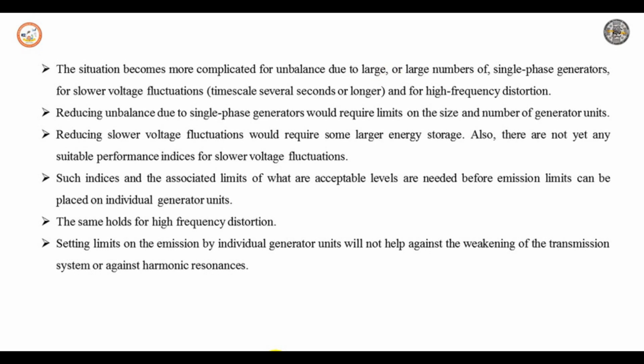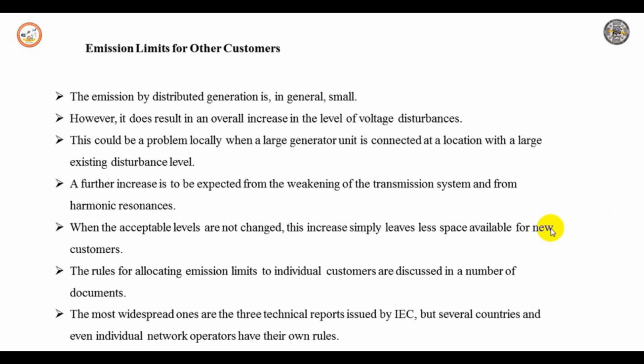This is about the emission limits for the generator unit. So let us see the emission limits for other customers. The emission by distributed generation is in general small. However, it does result in an overall increase in the level of voltage disturbance. This could be a problem locally when a large generator unit is connected to a location with a large disturbance level. A further increase is to be expected from the weakening of the transmission system and from harmonic resonance.